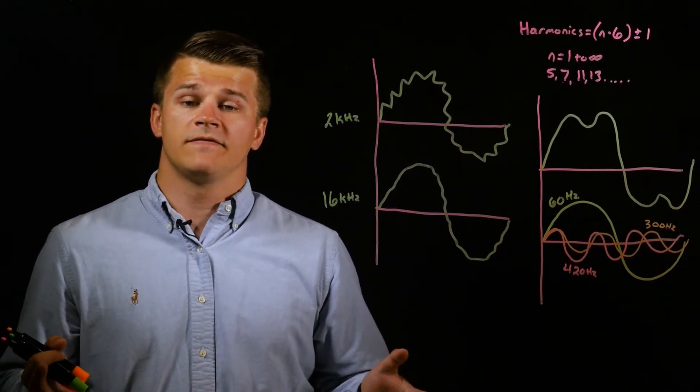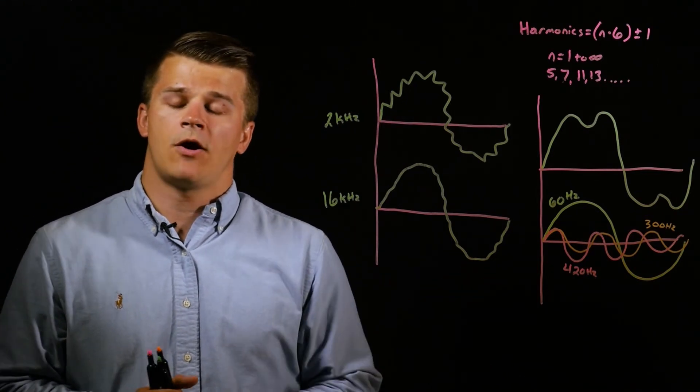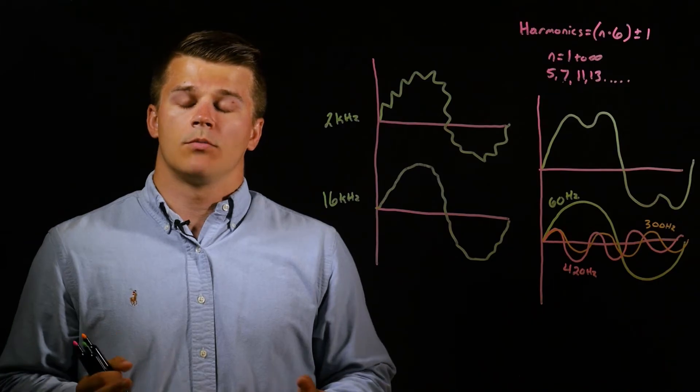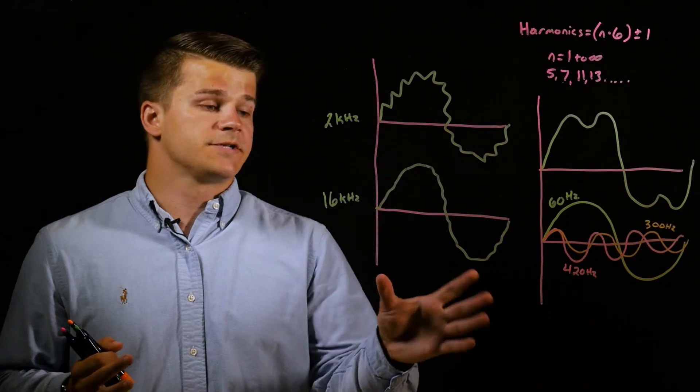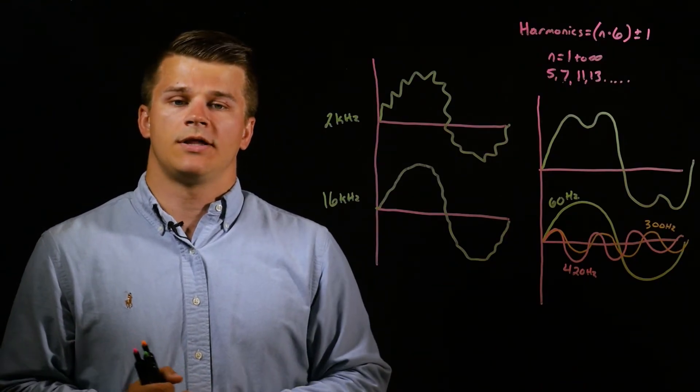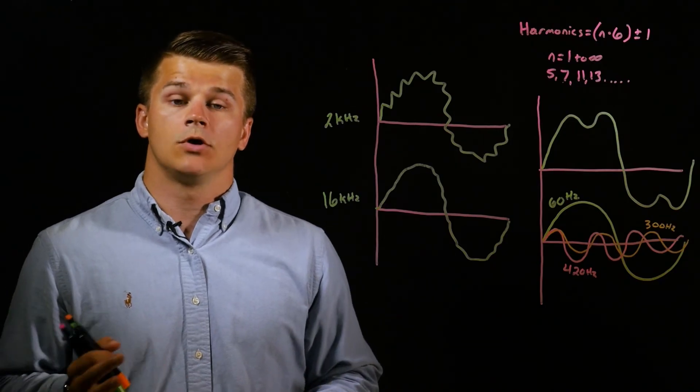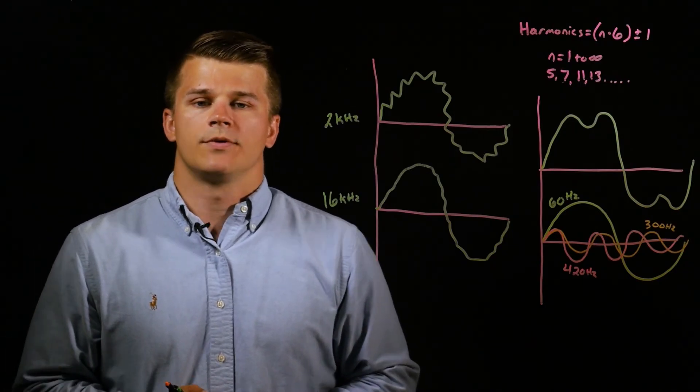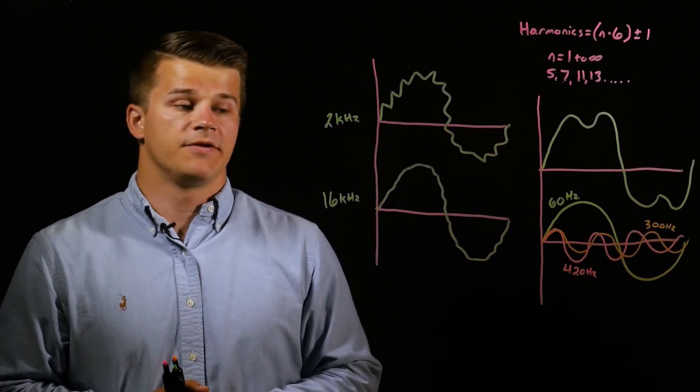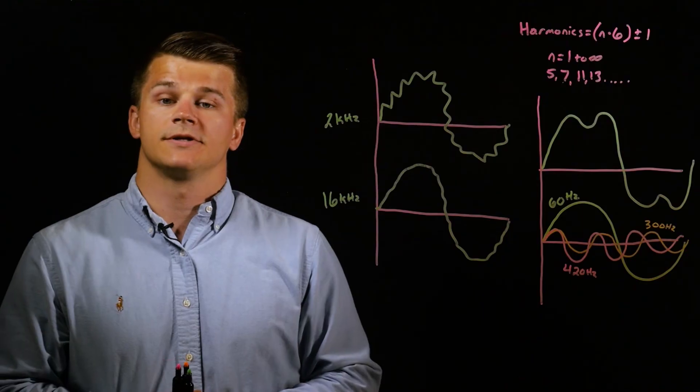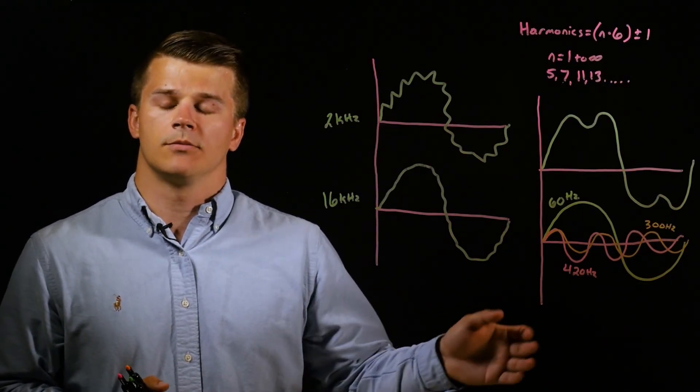There are a lot of advantages that come with increasing the switching frequency. The biggest is because you have this cleaner output waveform, you'll have lower motor losses and thus higher efficiency in your motor. This output waveform will also allow for lower motor heating, which can increase the lifetime of your motor and produce lower audible motor noises. So in applications such as in the theater industry, you'd have quieter motor operation. And finally, because this effect is more pronounced at higher speeds, this higher switching frequency would allow you to reach a higher speed in your motor.